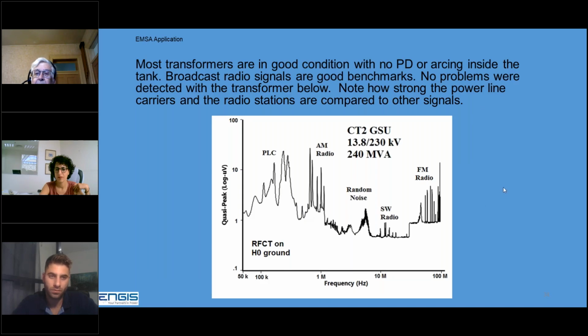The other thing is this is a frequency domain analysis, frequency versus amplitude. Partial discharge analysis is amplitude versus time. So it's a different way of looking at it. The mechanical problems, like arcing shaft ground brushes and that sort of thing, PDA can't pick up.